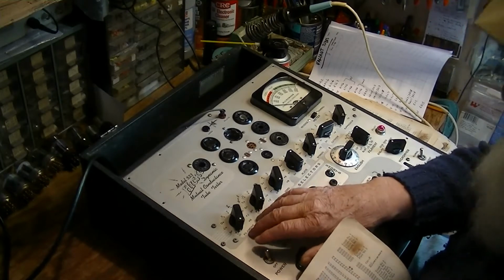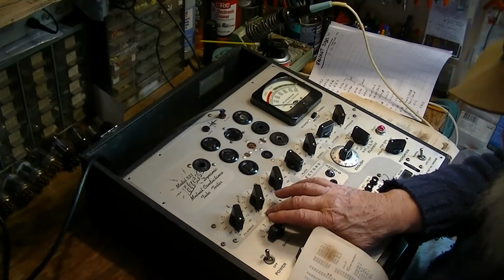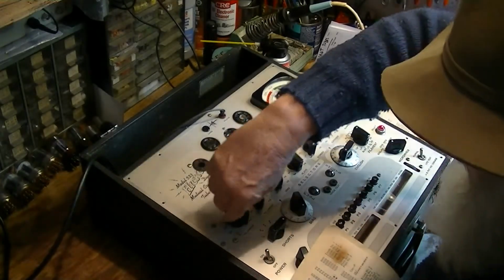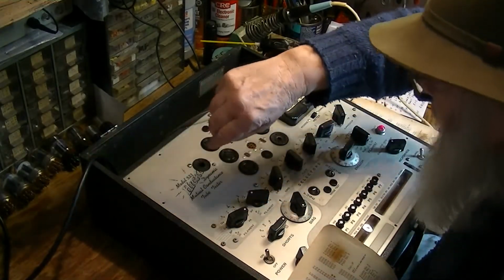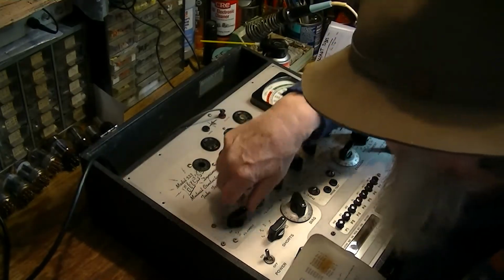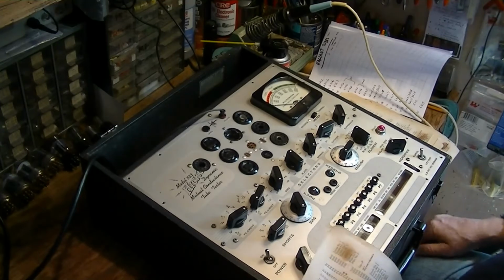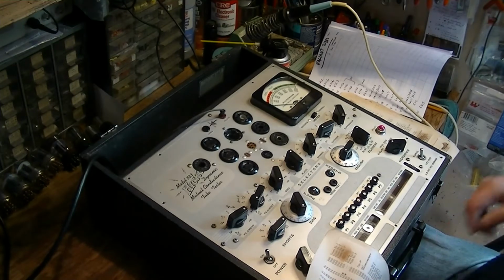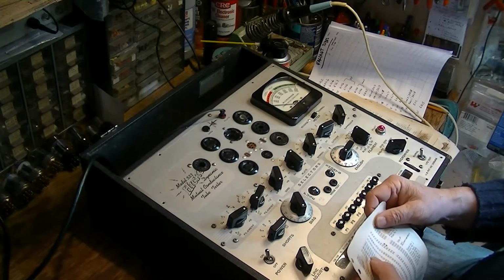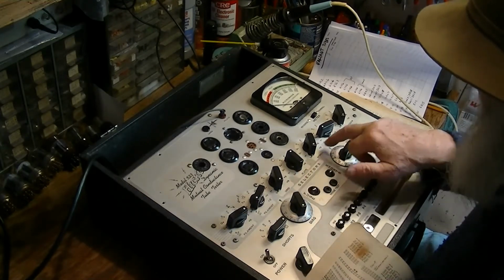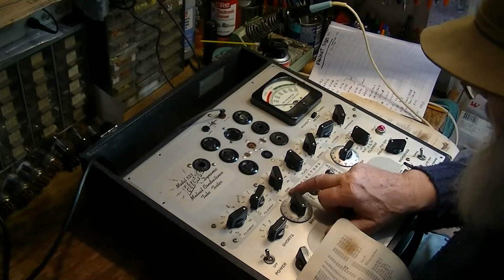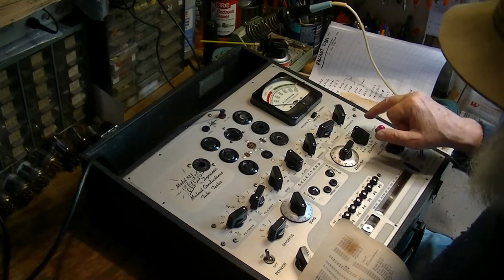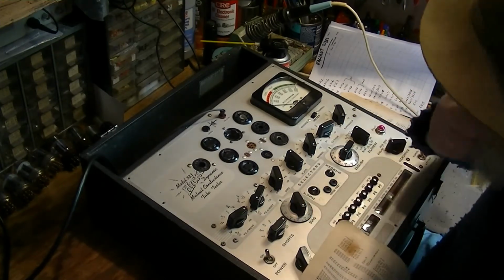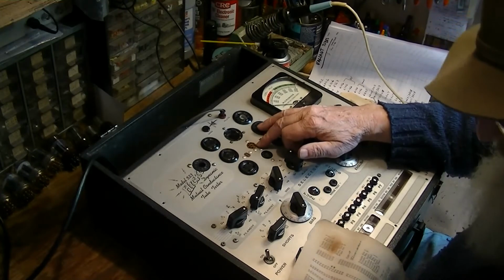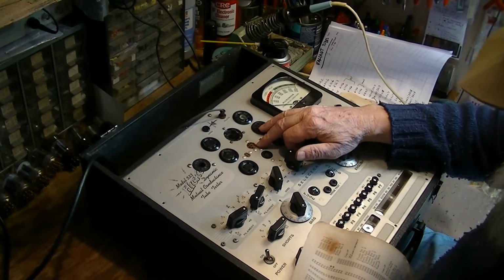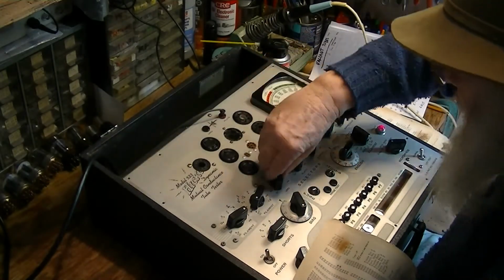Now we're going to go over here and assign the filament voltage to the right pins. In this case, it's JR, which is one of the very common settings. So we're going to set that to J, and we're going to set that to R. And that makes sure that the filament voltage shows up on the right pins on the socket. And next we're going to go and set these 1, 2, 3, 4, 5 switches, which are labeled, luckily, grid, plate, screen, cathode, and suppressor. And what this is going to do, in this case we're looking at a 7-pin miniature socket, this is going to assign the grid connection to the proper pin. In this case, it's pin 6, so grid 6.